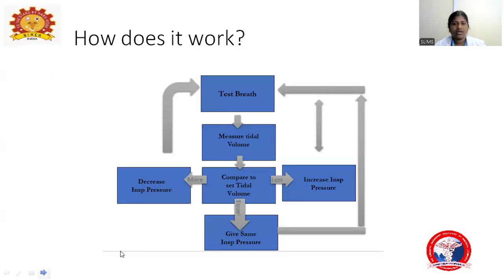So how does it work? The ventilator will give a test breath and measure the tidal volume. It will compare the measured tidal volume to the set tidal volume.